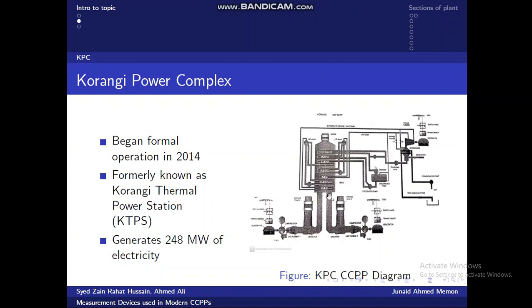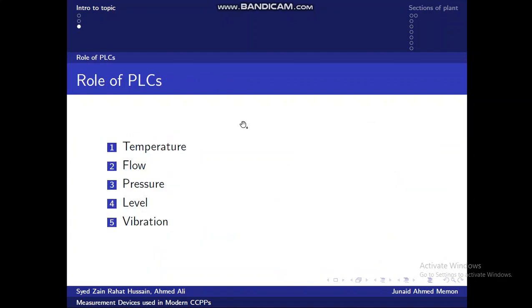As you can see here, this is a diagram showing KPC. So we have the 2 gas turbines here, and then we have the steam turbine here. So there's only one present, but there's another one. The programmable logic controllers are present throughout the plant. They continuously send data to the control room for proper operation and monitoring of the different systems. The 5 main parameters that are measured include temperature, flow, pressure, level, and vibration. Some of the common examples of these are thermocouples for temperature, strain gauges for pressure, ultrasound wave propagation for level, and eddy currents for vibration.